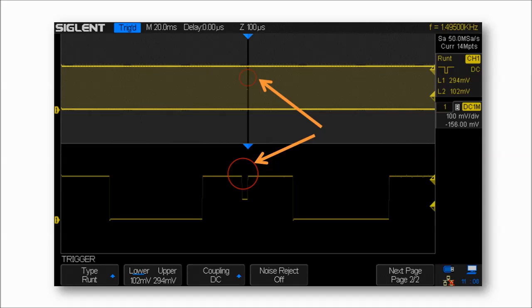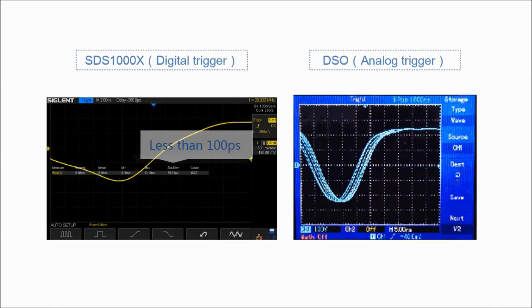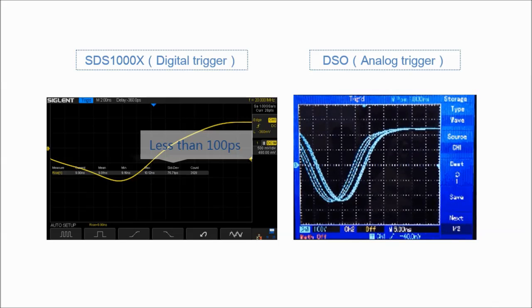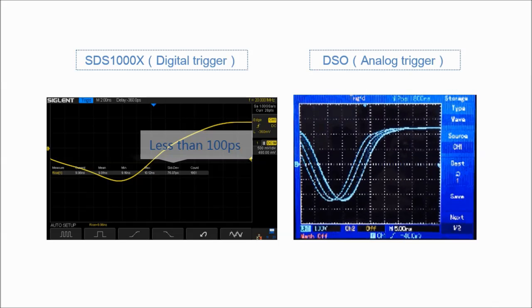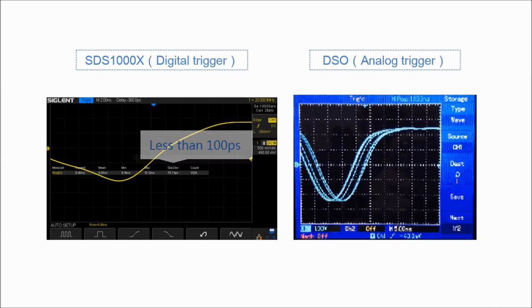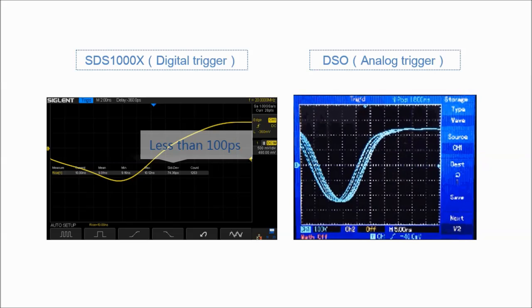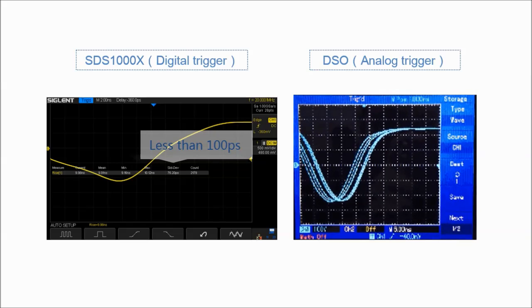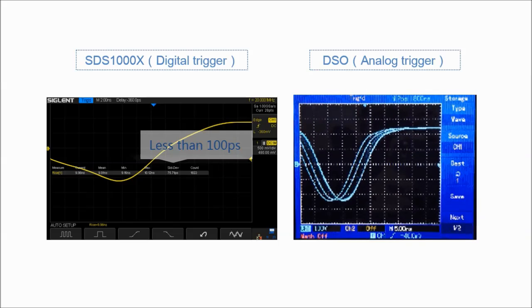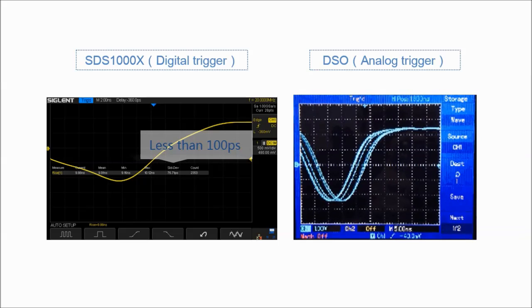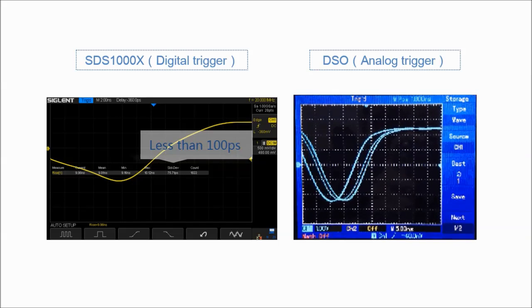The SDS-1000X also uses an innovative digital trigger system with high sensitivity and low jitter. This system limits trigger jitter to less than 100 picoseconds.